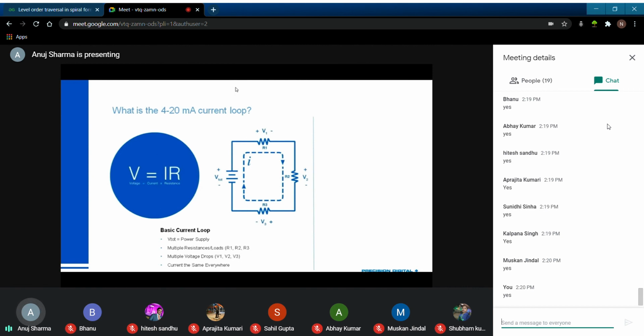Then I've got the different elements that are connected up in my current loop. I've got R1, R2, and R3, which are modeled as resistors, but really could be any kind of load. That could be a panel meter or a PLC. It could be a transmitter, a chart recorder, anything that is connected up to that loop. Each one of those devices, because it has a unique R, is going to have its own voltage drop.